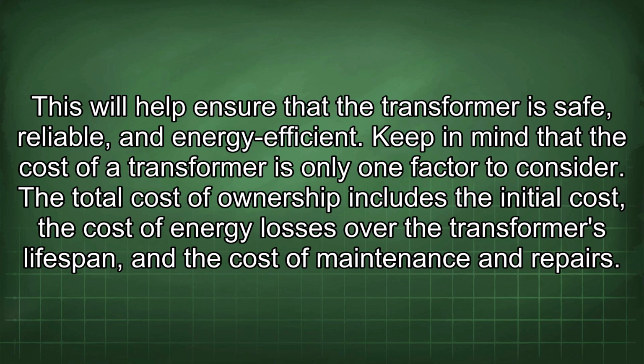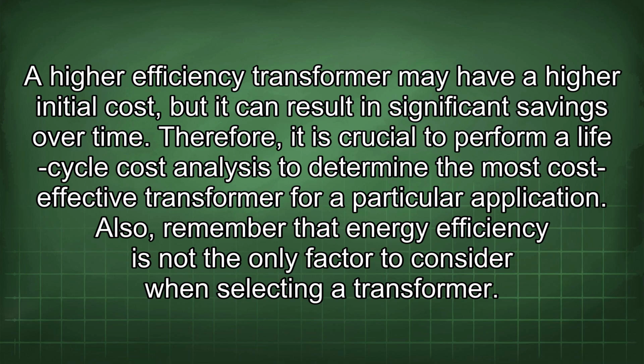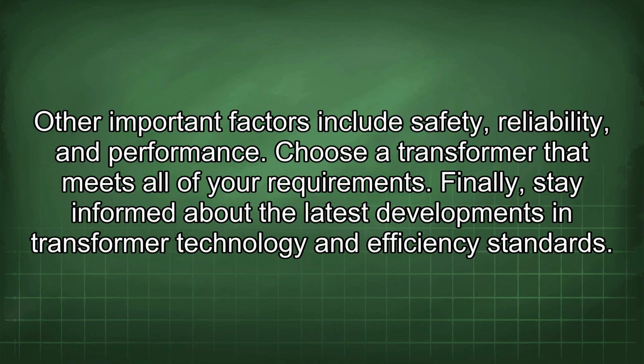reliable, and energy efficient. Keep in mind that the cost of a transformer is only one factor to consider. The total cost of ownership includes the initial cost, the cost of energy losses over the transformer's lifespan, and the cost of maintenance and repairs. A higher efficiency transformer may have a higher initial cost, but it can result in significant savings over time. Therefore, it is crucial to perform a life cycle cost analysis to determine the most cost-effective transformer for a particular application. Also, remember that energy efficiency is not the only factor to consider when selecting a transformer. Other important factors include safety, reliability, and performance. Choose a transformer that meets all of your requirements.